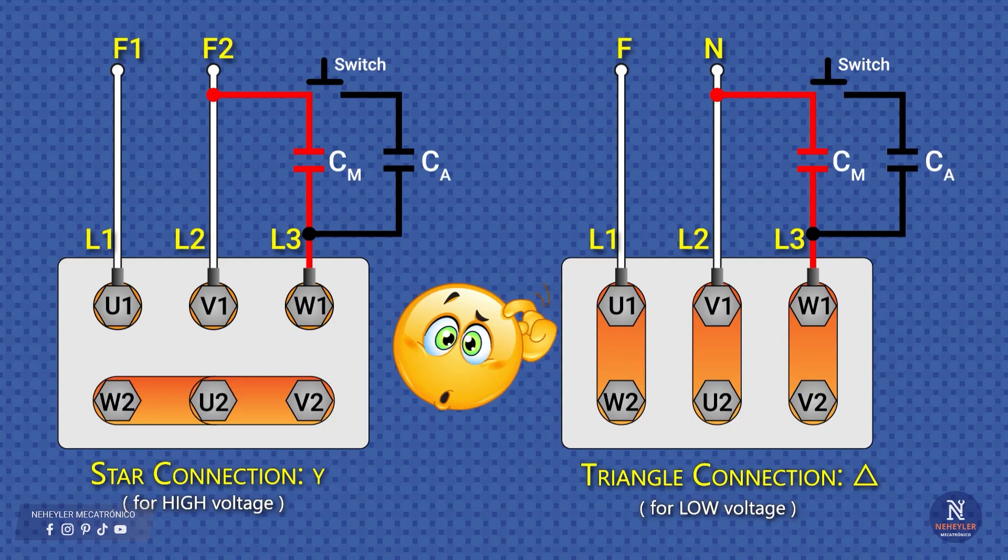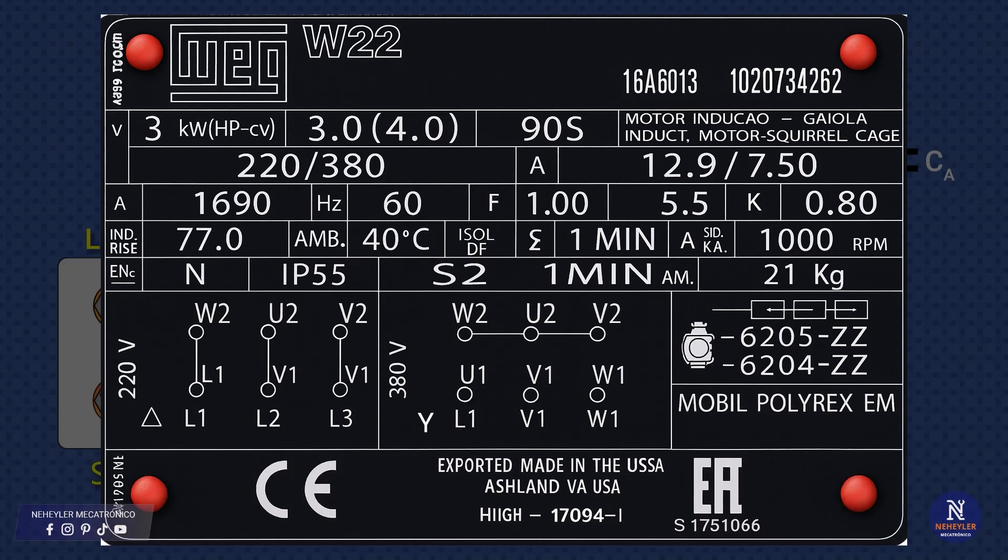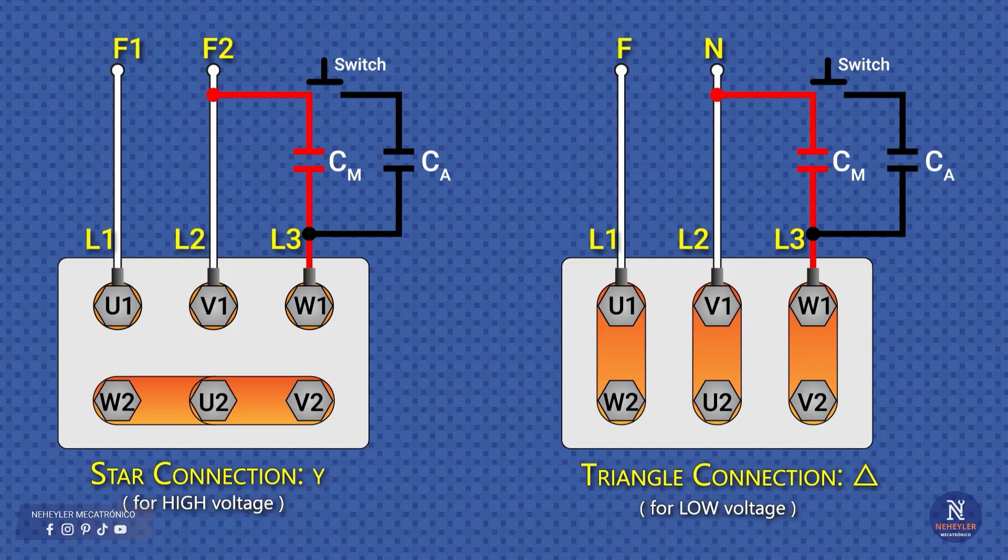Now then, how do we choose between star or delta? The answer is on the motor nameplate. For example, this motor indicates 220 volts for delta connection and 380 volts for star connection. Now let's see how the capacitors come in.